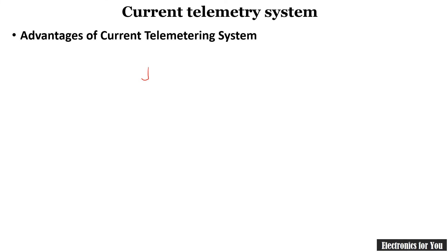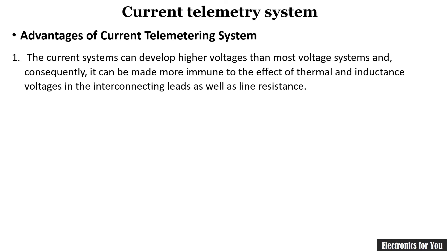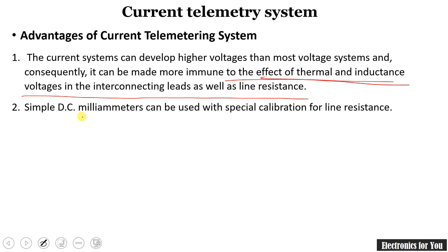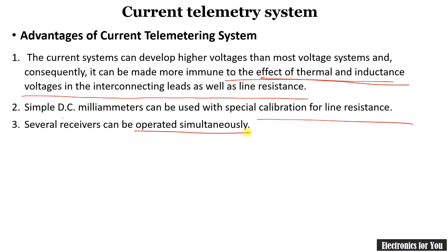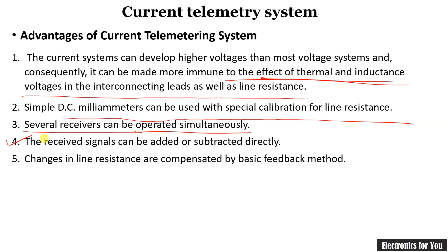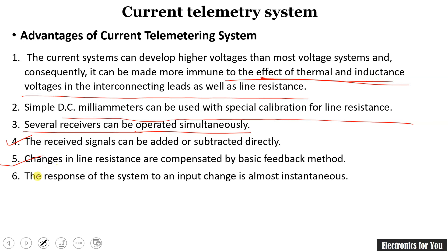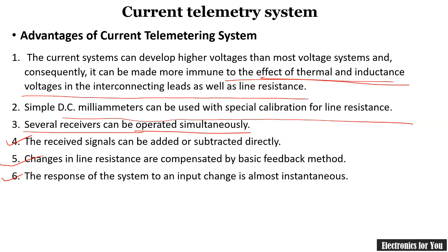The advantages of the current telemetry system are: it is immune to the effects of thermal and inductance voltage in the interconnecting leads as well as line resistance. A simple DC milliammeter can be used with special calibration of line resistance. Several receivers can be operated simultaneously. The received signal can be added or subtracted directly. Changes in line resistance are compensated by the basic feedback method. The response of this system to input is almost instantaneous.